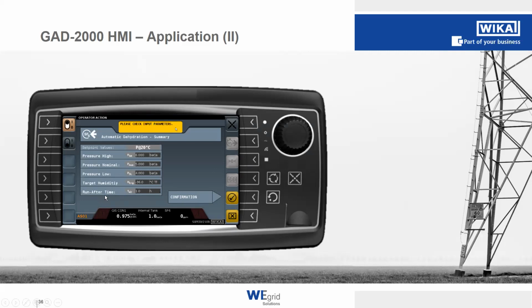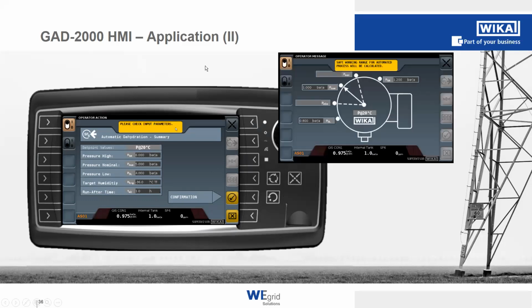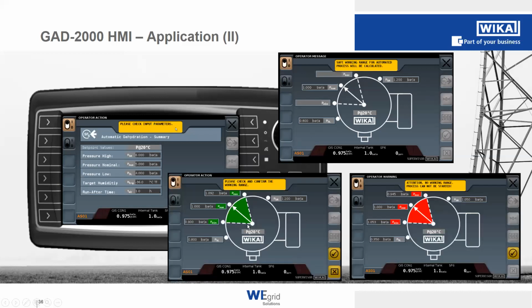And then we also can set the run after time. This was the T diffusion time 2, which I described with the longer time period. So in the graphs before, the time was set to 48 hours. After we put in the values, we confirm that, and we can start our dehydration process. Not immediately, because the GAD will also recheck the values you entered, and it will calculate the safe working range for you. And if the working range is okay, like the values are all right for the system, it shows you with the green graphics. If the values you entered are not acceptable, then the GAD tells you and shows that you have to re-enter the values.